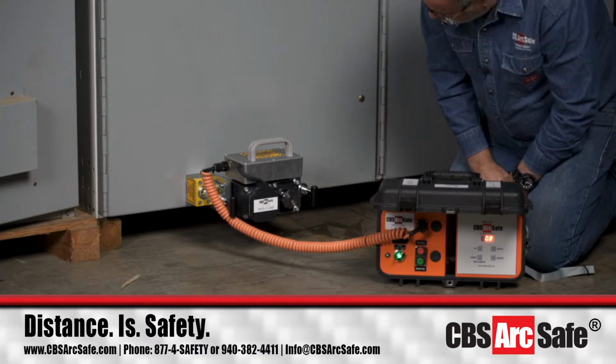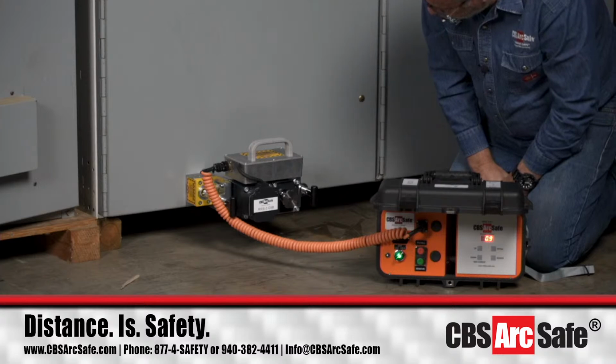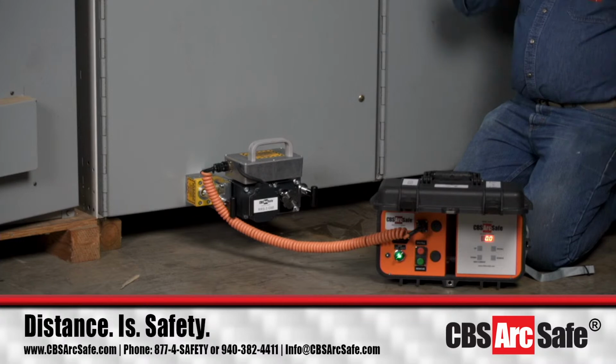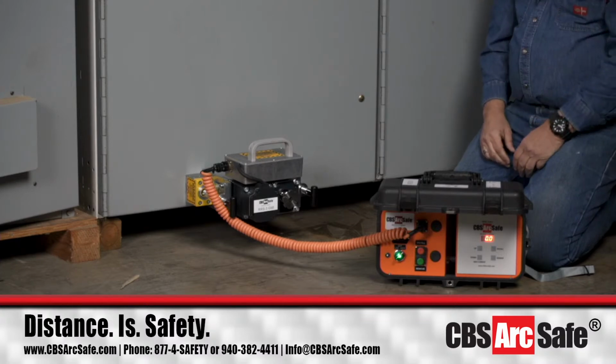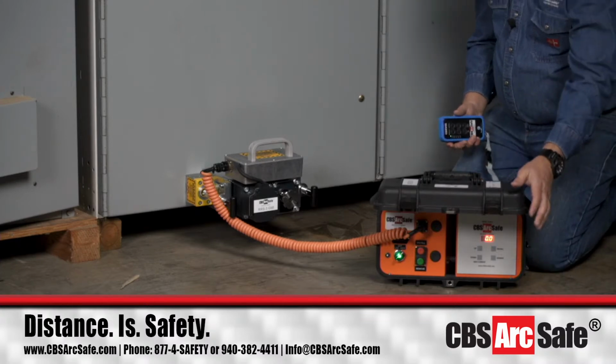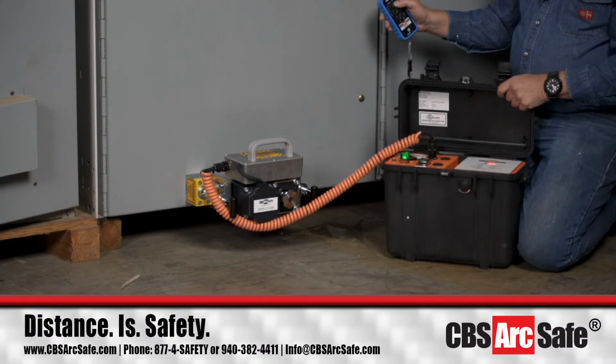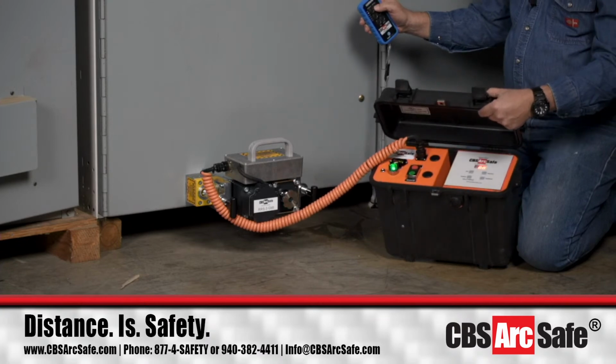And we're just about there. And it automatically shuts off due to torque, hitting the torque limit on the bottom side. To install the breaker, okay, all we have to do then is depress the install button now, and you'll see the same thing happen in reverse.